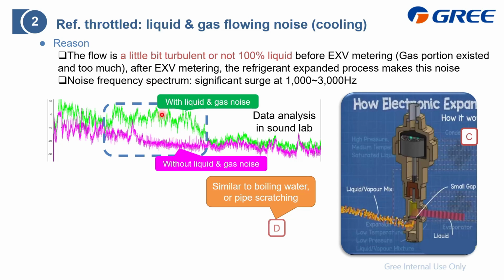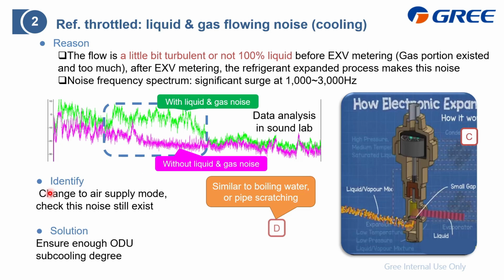As we know the reason, our countermeasure or solution is very simple. First of all, how to identify this one? You need to change your problem indoor unit from cooling mode to air supply mode. If this noise just disappears, then you can confirm it, right? And this solution is just to ensure the outdoor unit subcooling degree, which is to ensure the liquid out from the outdoor unit is subcooled enough.